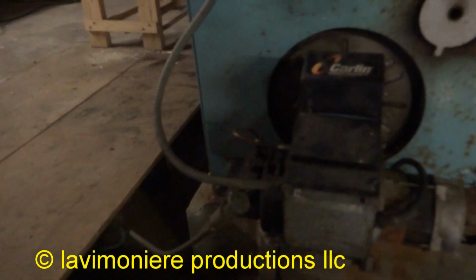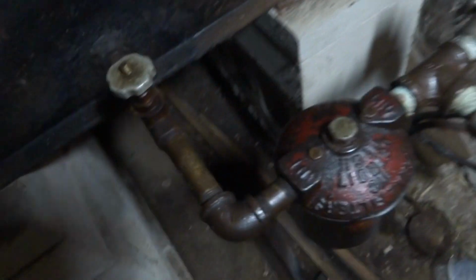There's no filter on it. Suntecs have filters. This one's got a Suntec, I know it's got a filter. When was the last time I serviced this thing? 2016. Guys, remember I disconnected this tank here and hooked them both up to this one. OSV valves. So we'll change this filter just for the heck of it.